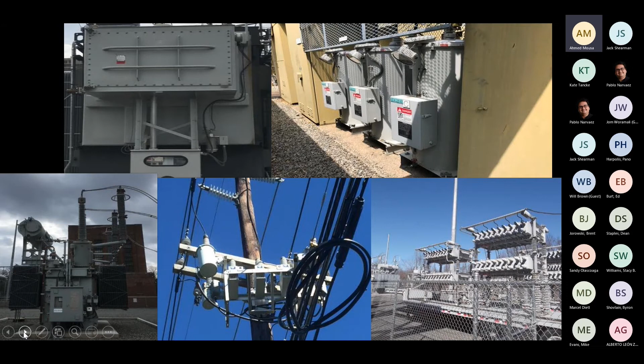The picture on the left is the 1 megavar StatCom. We installed 2 of them at the far end of our territory near Atlantic City, near a large solar farm. Traditionally, with a tap changer, the time delay may be 90 seconds, 60 seconds or so—you need enough time delay between the tap changer, the voltage regulator, and the cap banks, especially with multiples of them per circuit, per substation. Now, this device changes status 30 times a second.